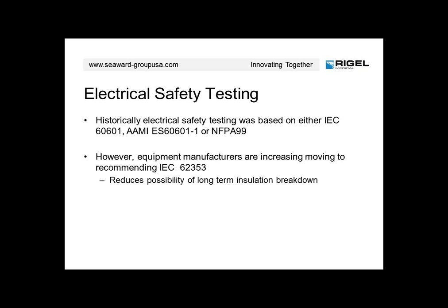However, in discussions with a lot of equipment manufacturers, they're starting to move to the IEC 62353 standard. There are a couple of things associated with that we'll dive into, but one of the best reasons to move in that direction is that it reduces the possibility of long-term insulation breakdown from doing high current testing or high pot testing of the individual products themselves.